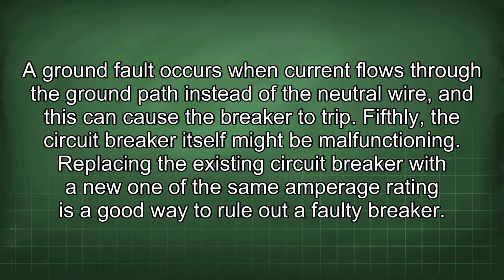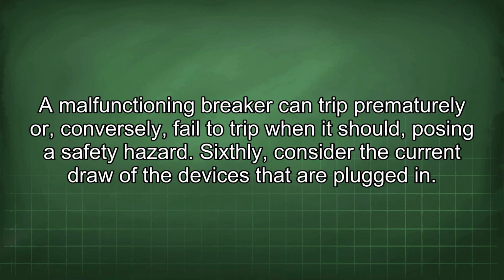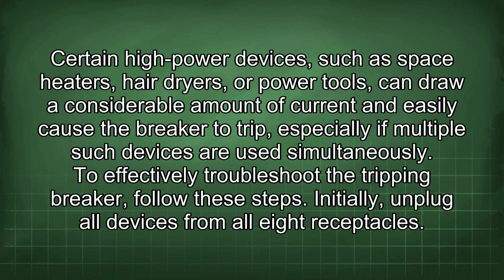Replacing the existing circuit breaker with a new one of the same amperage rating is a good way to rule out a faulty breaker. A malfunctioning breaker can trip prematurely or, conversely, fail to trip when it should, posing a safety hazard. Sixthly, consider the current draw of the devices that are plugged in. Certain high-power devices, such as space heaters, hair dryers, or power tools, can draw a considerable amount of current and easily cause the breaker to trip, especially if multiple such devices are used simultaneously.